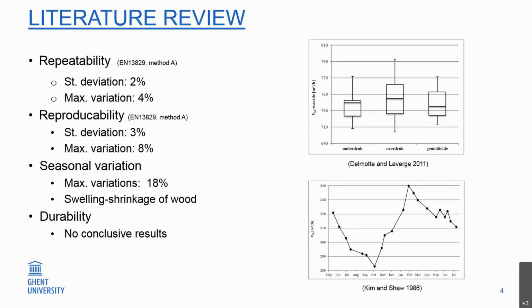For the reproducibility conditions, the same building was tested 10 times by different operators, bringing their own equipment, also on different test days. So in the first case, we see a standard deviation of 2% and a maximum variation of 4%. These numbers rise to 3 and 8% under reproducibility conditions as a result of the impact of building preparation, building equipment, and weather conditions.